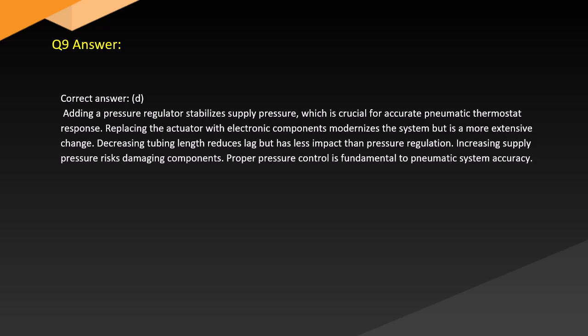Answer. Correct answer: D. Adding a pressure regulator stabilizes supply pressure, which is crucial for accurate pneumatic thermostat response. Replacing the actuator with electronic components modernizes the system but is a more extensive change. Decreasing tubing length reduces lag but has less impact than pressure regulation. Increasing supply pressure risks damaging components. Proper pressure control is fundamental to pneumatic system accuracy.